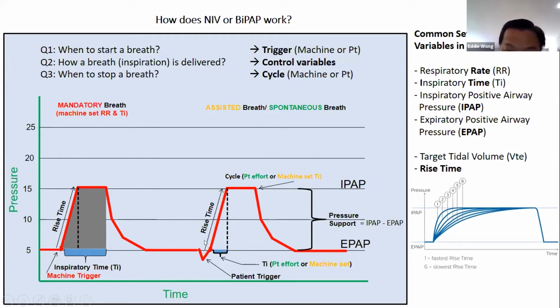And how much the pressure rises to enter the air into the lung for oxygenation depends on the IPAP and EPAP setting. So pressure rises based on the IPAP you set, the lung will close based on the EPAP setting. So you see here the lung will open and close, which means the air will move inside the lung and out of the lung by using these two levels of pressure called EPAP and IPAP. So when you subtract these two pressure levels, IPAP minus EPAP, this is called pressure support. Sometimes when we talk to the doctor, we ask the doctor, how much pressure support do you need for this patient?